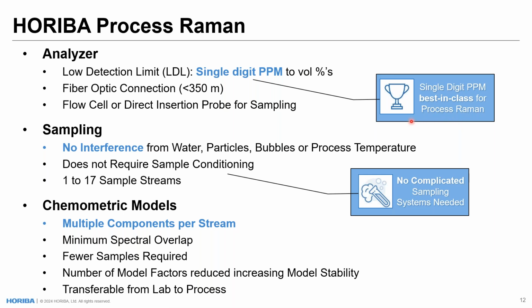A lot of our competitors and a lot of other analyzers out there can really only get down to volume percents or half volume percents, we'll say, but we can readily and proudly get down to single-digit ppm with our process analyzers. Likewise, our fiber optic connections to our analyzers allow for flexible analyzer placement, which totally reduces installation requirements and constraints for an end user. So that headache can be taken away if we can set up that analyzer up to 350 meters away from their process line.